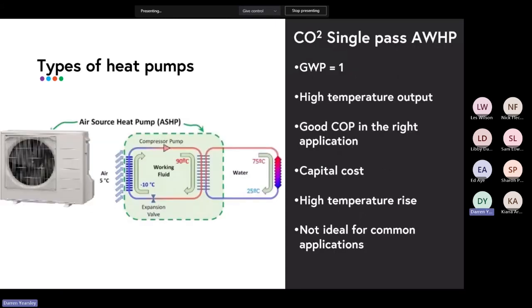Okay, so another very common technology in the market at the moment when it comes to air to water heat pumps, if you want to produce domestic hot water, a very good technology, or one which has got some significant advantage over the R134A and over the R32, is CO2. So a CO2 heat pump, we call it a single pass air to water heat pump. I'll explain why that is in a minute. It has the gold standard in terms of GWP, a GWP of 1.